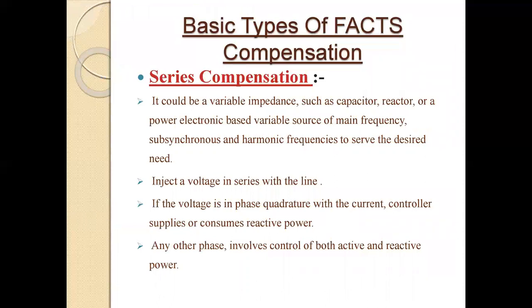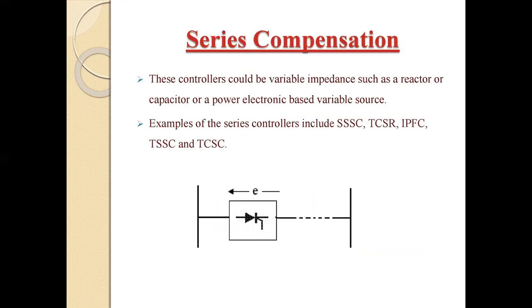Now we discuss series compensation. It could be a variable impedance such as a capacitor or reactor, or a power electronic based variable source of main frequency, subsynchronous, and harmonic frequencies to serve the desired need. It injects a voltage in series with the line. If the voltage is in phase quadrature with the current, the controller supplies or consumes reactive power. Any other phase involves the control of both active and reactive power. Examples of series controllers include SSSC, TCSR, IPFC, TSSC, and TCSC.